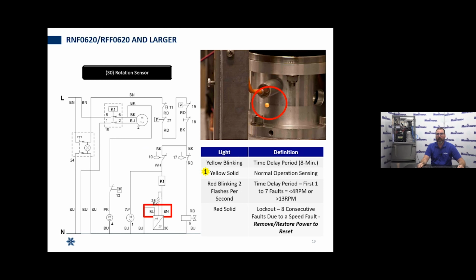Now, if you see red fast flash, 2 flashes per second, what we call fast flash, that's indicating that we had a fault. Up to 7 times, we are going to stop and reinitiate that 8-minute time delay period, and hopefully after that 8 minutes expires, we'll have rotation again. But if you see the red fast blinking light, that indicates that we have lost RPM at some point and that we are starting over on that time delay period. Now, if you see that red light go solid, or you come up to a machine where that red light is solid, that means it has tried 8 times to establish RPM and it has failed all 8 times.